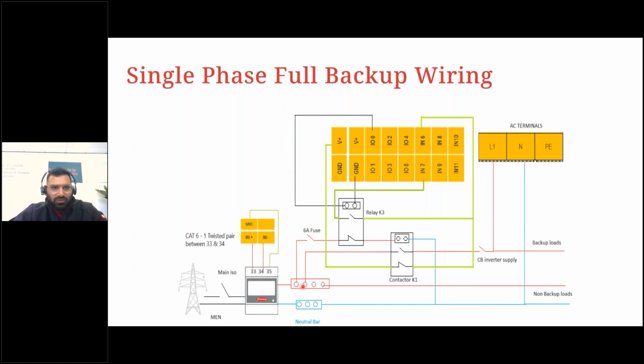So let's take a look here. We have a normally open connection going towards the load, and the power supply of the contactor is coming through the normally closed of the relay, and the actual relay gets power supply from the inverter pin IO0, and it's connected to the ground as well, of course, to complete the circuit. Now, what is the other thing that we need? How does the inverter know that the contactor and relay have worked and it is okay and safe to run the system in backup, and that if the grid comes back again, we will not simply connect back to the grid while the inverter is still running in backup?